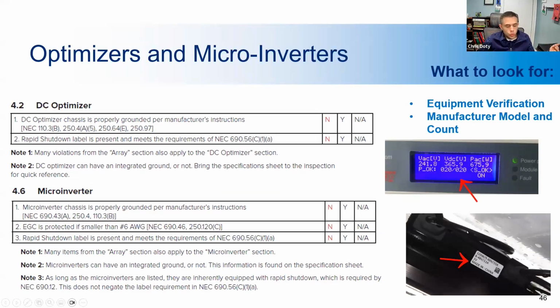All right, so optimizers and microinverters. As I mentioned earlier, a DC optimizer is essentially a DC to DC converter that takes whatever amperage and voltage is produced at the solar panels, because it varies throughout the day, and converts it to the voltage and amperage required by the string inverter. Microinverters are essentially an inverter on each panel, like a small inverter, as the name indicates. So all wire runs in a microinverter setup are AC electricity as opposed to DC. And then they bring it all together in an AC combiner panel. So we'll take a quick look at that.